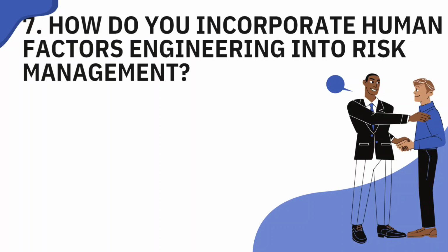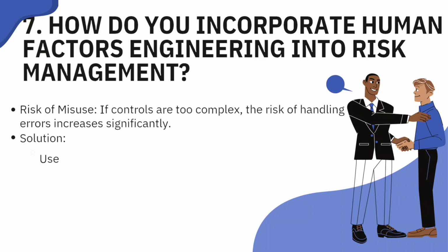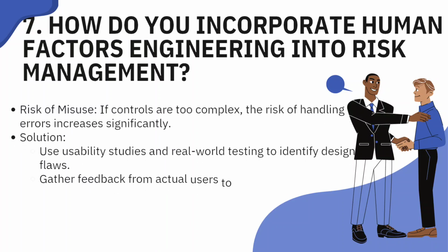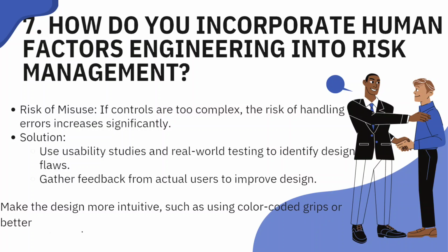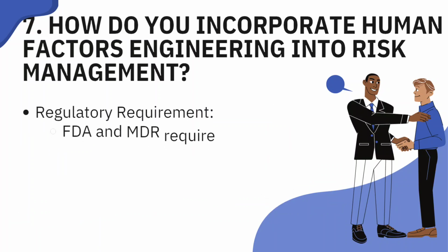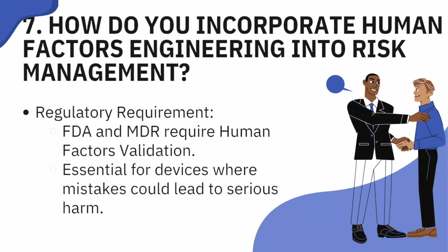Human error is one of the biggest risk factors. That's where human factors engineering, HFE, comes in. Let's say we're designing a surgical tool. If the controls are too complex, the risk of misuse or handling errors skyrockets. Through usability studies, real-world testing, and feedback from actual users, we can make the design more intuitive, maybe with color-coded grips or better ergonomics. Regulators like the FDA and MDR require human factors validation, especially for devices where mistakes could lead to serious harm. Absolutely.